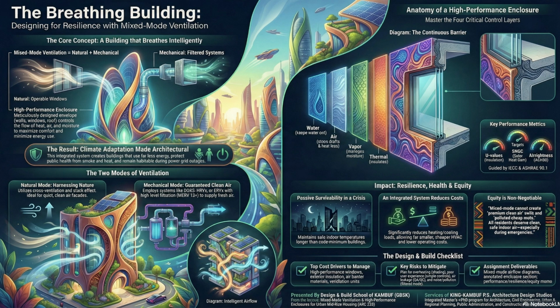And given the need to switch into that red zone during, say, a smoke event, the building needs to be monitoring the air, not just the weather. Yes. High-performance buildings use sophisticated monitoring. We rely on CO2 sensors to measure indoor air quality related to how many people are in a space. That can trigger a boost if the air gets stale. But now you need more.